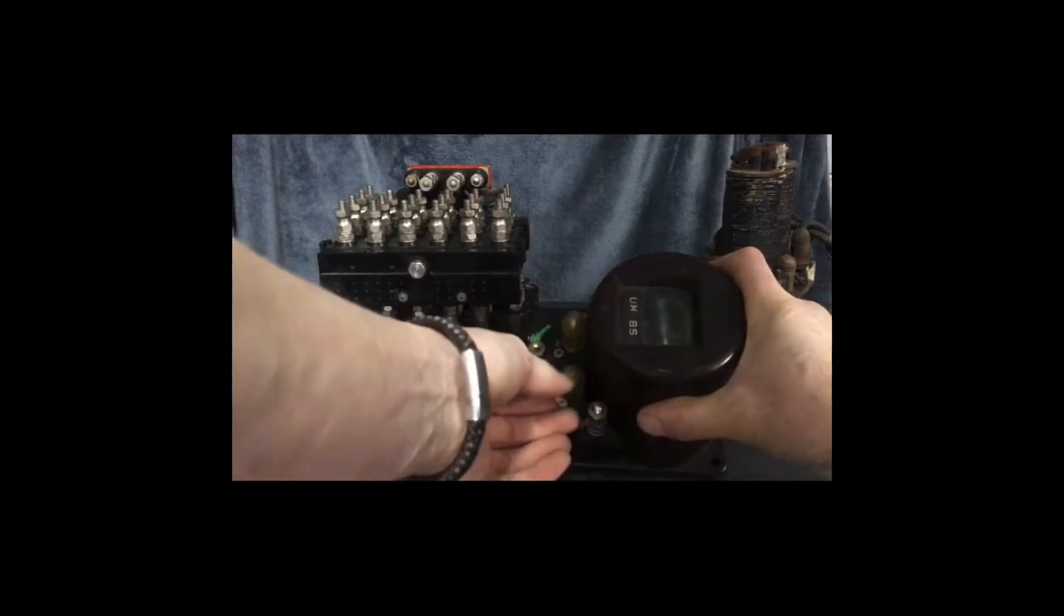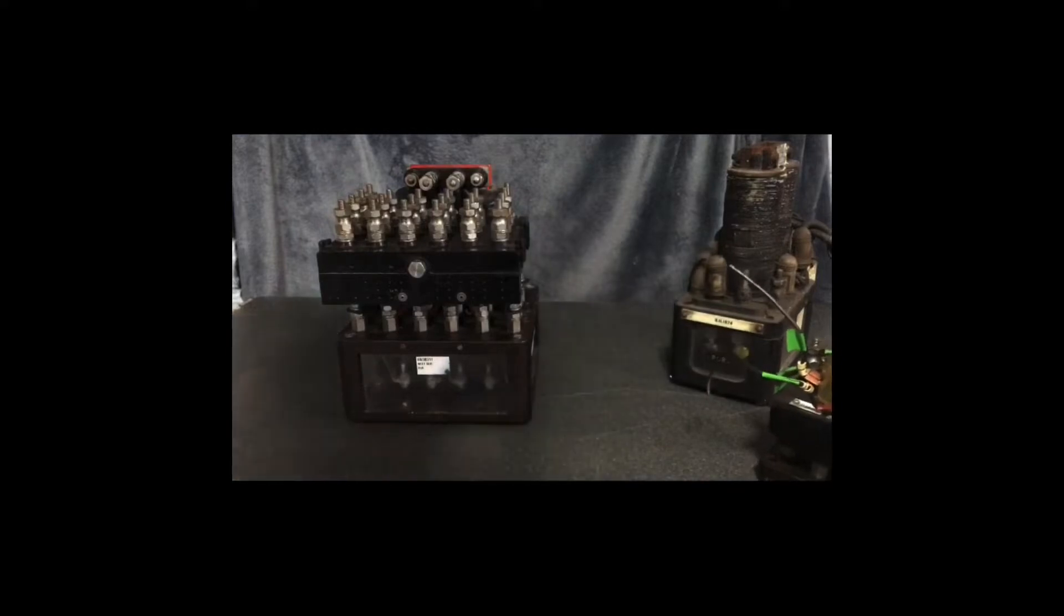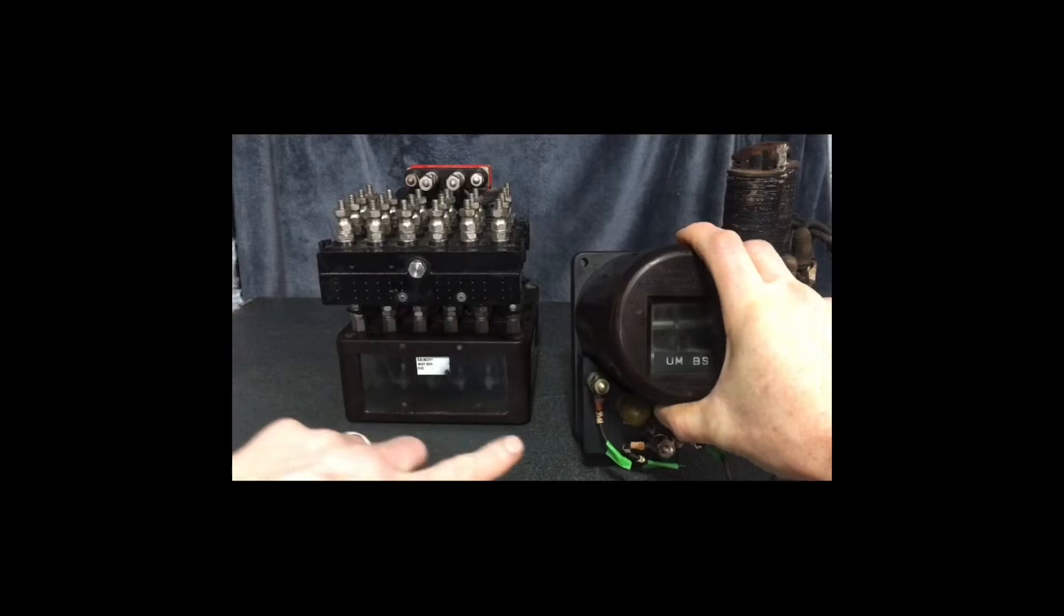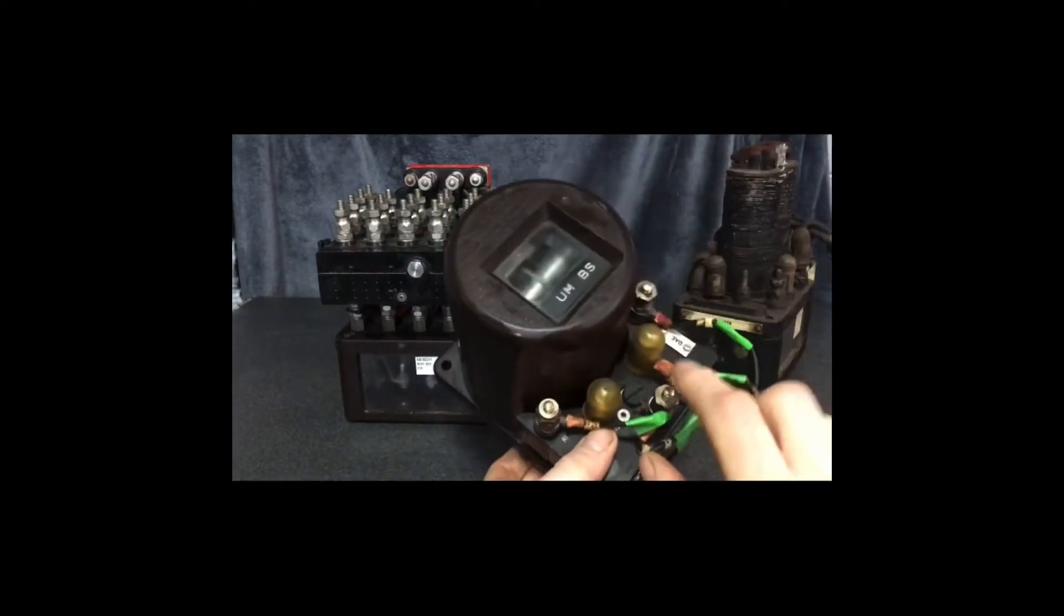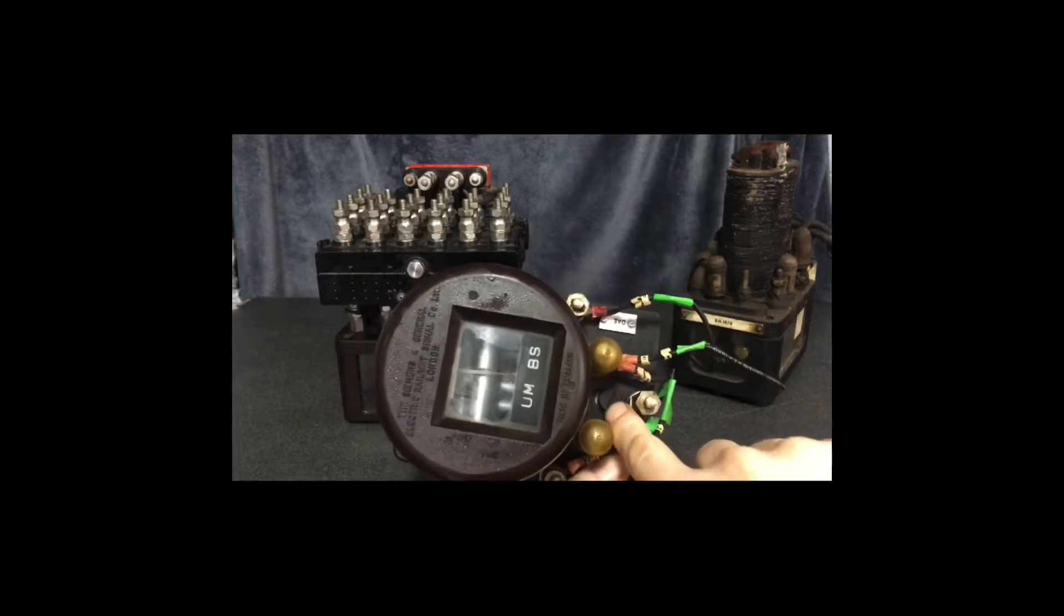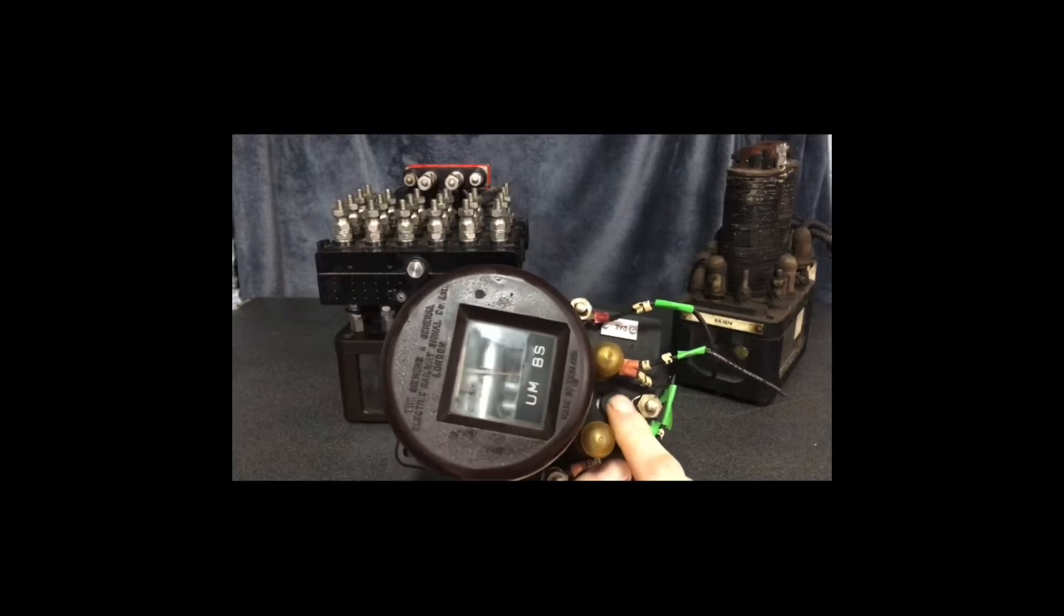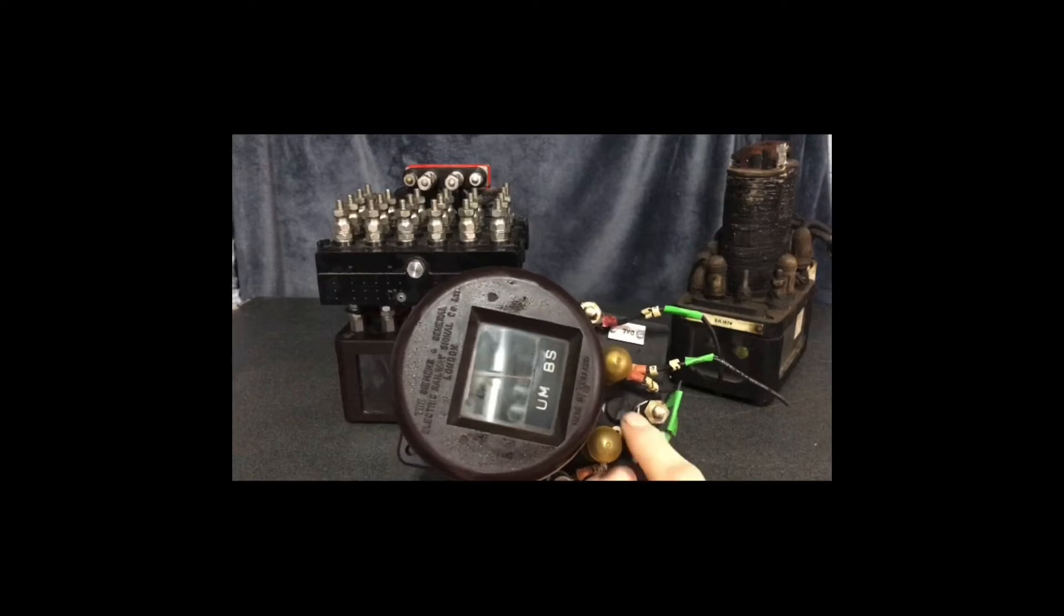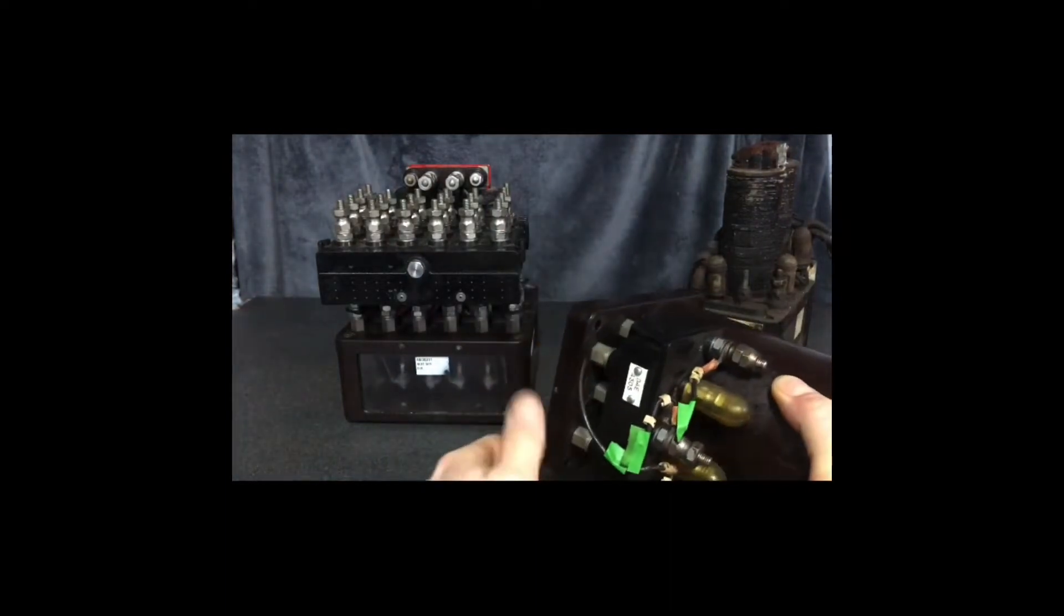Traditionally there's a small plastic plate on here that also gives you that serial number of the pin code. Even on this one there is a pin code. What you have is a Bakelite screw there. Later ones do have steel ones. These Bakelite ones were well known if they sat on the shelf for about 10-15 years, they just seize in. Later ones do have a different make of screw to get that off. This just comes off again and unplugs and you put your new relay in.